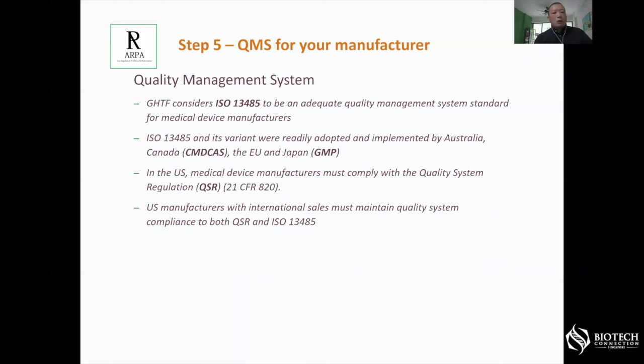Okay, how does it work in the whole world, including US, Europe, etc.? Globally speaking, including Europe, ISO 13485 is the golden standard. If you are a medtech company, this is the standard I would highly recommend you follow. And how about the whole world? It is relatively straightforward. I would say the core is still 13485, but they will add or subtract some local requirements and make it their local requirement. Like in Canada, they don't call it ISO 13485, they call it CMDCAS, which is like 13485 plus minus something. And in the US, they call it QSR, etc.